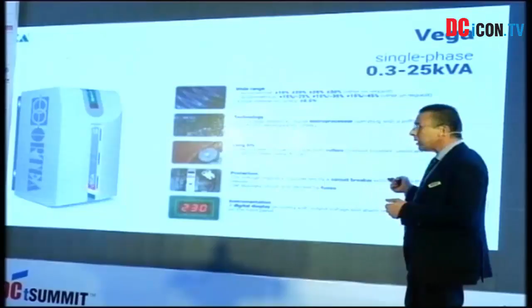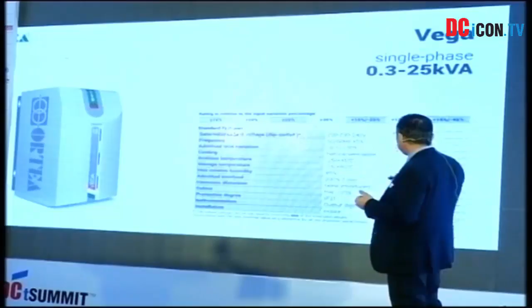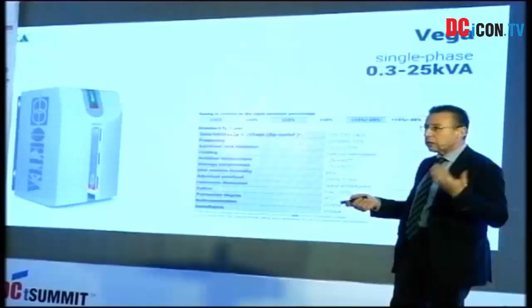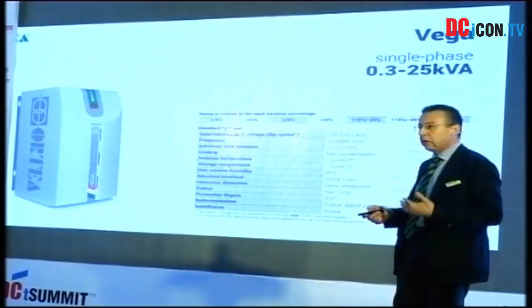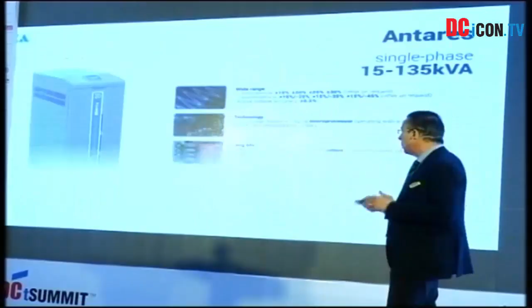So there is a concept in our company that for the variation in input, you can see that we have what we call balanced or symmetrical variation, plus minus at the same value, or unbalanced input variation. So plus 15 minus 25, plus 15 minus 35, or plus 15 minus 45. You know very well that at minus any value, so minus 20 or minus 25 or whatever is the setting of the unit, you have the maximum current of that unit. So means that there is maximum stress of the unit. So this is very, very important, because our units will supply you the full load at the minimum voltage. So at the maximum current will supply you continuously the full load. This is valid for all the unit, either single phase or also three phase.